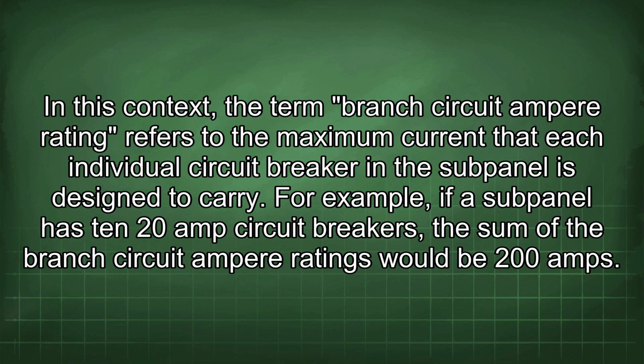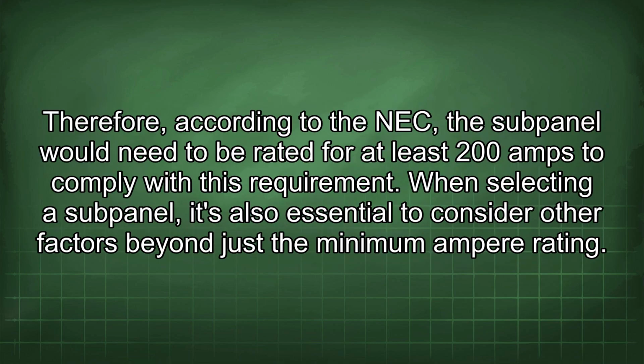For example, if a subpanel has ten 20-amp circuit breakers, the sum of the branch circuit ampere ratings would be 200 amps. Therefore, according to the NEC, the subpanel would need to be rated for at least 200 amps to comply with this requirement.